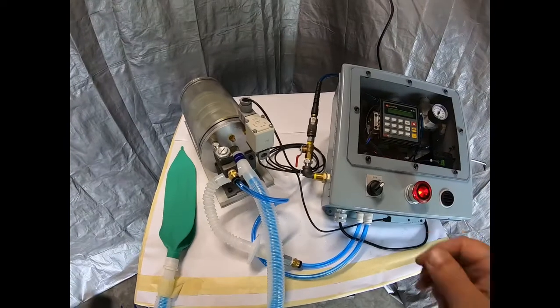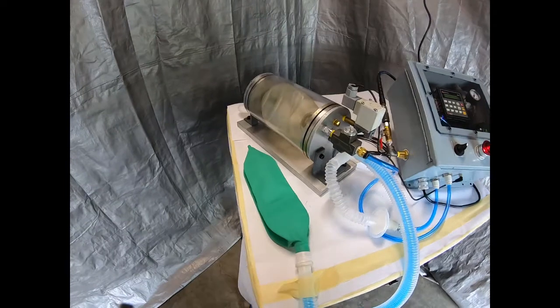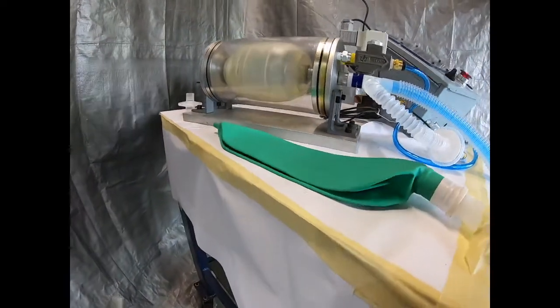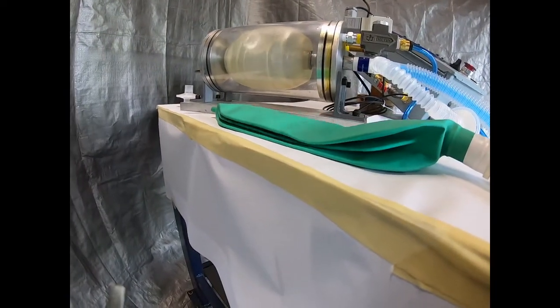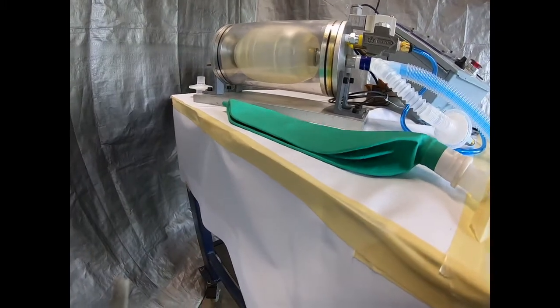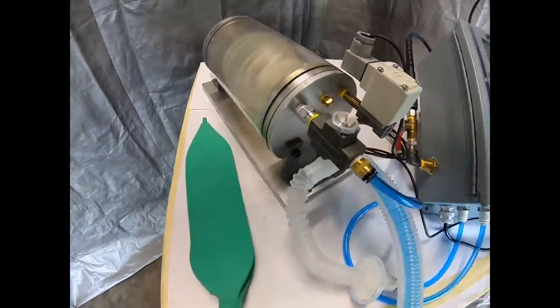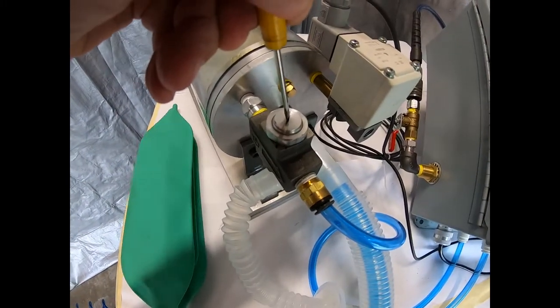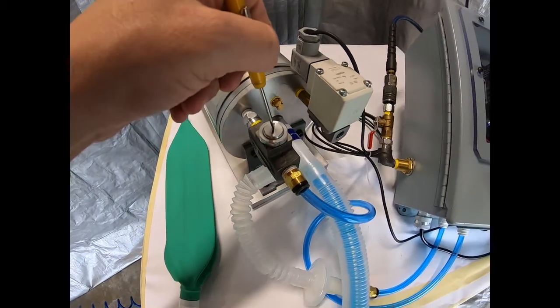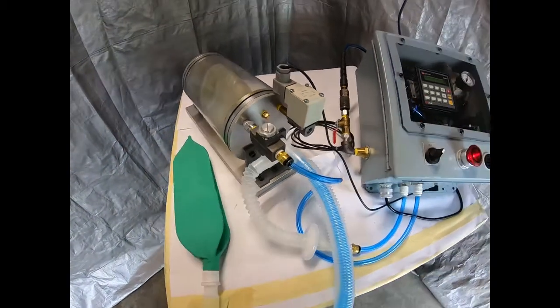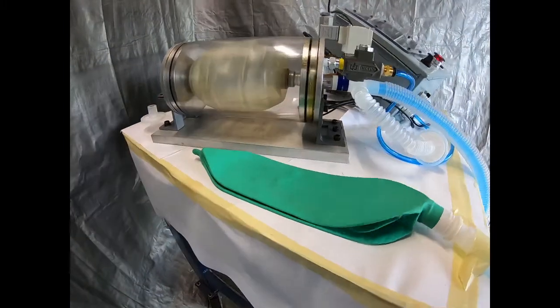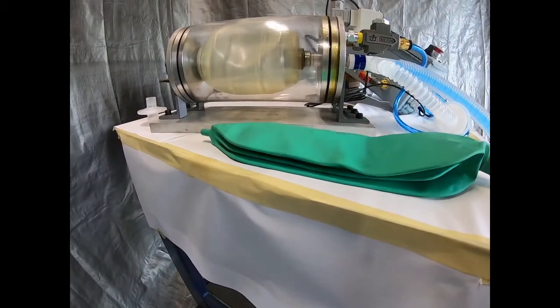It works on the principle of pneumatics. By placing the same BVM inside of a pressurized air chamber, we can both deflate and inflate the mask using changes in air pressure. This allows us a greater degree of control of the breaths that are delivered to the patient, since by inflating the mask faster than it would by simply absorbing atmospheric air, we can actually change the volume and speed of breaths that are delivered to the patient.